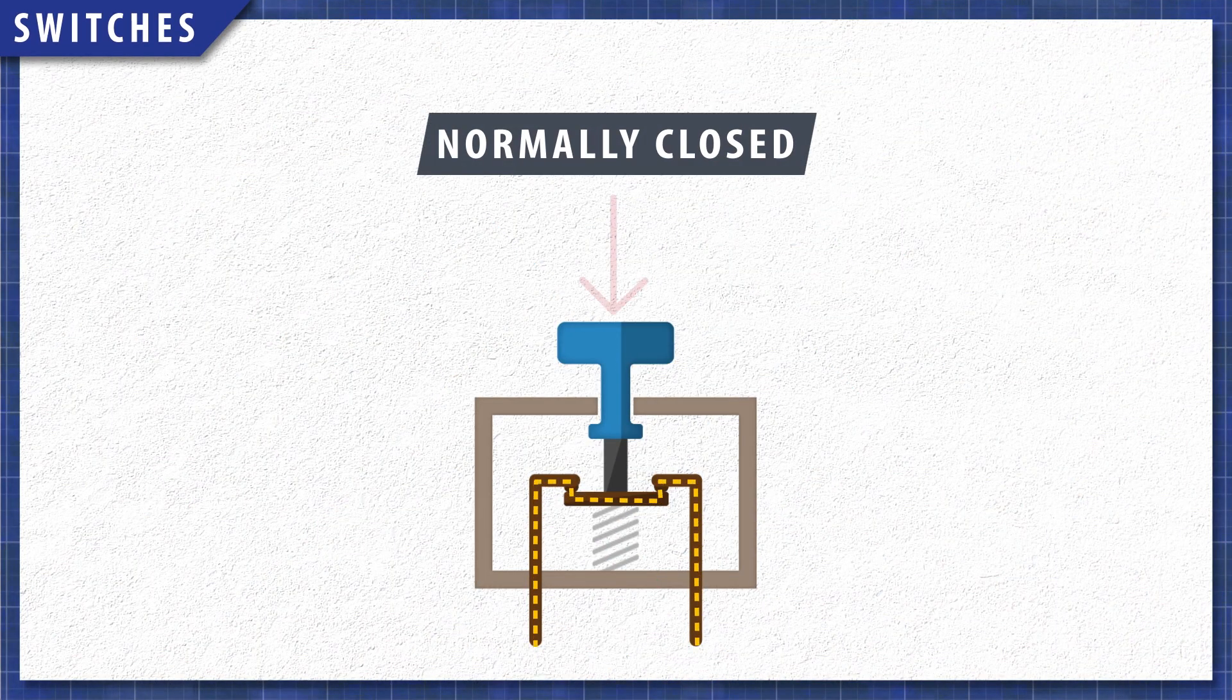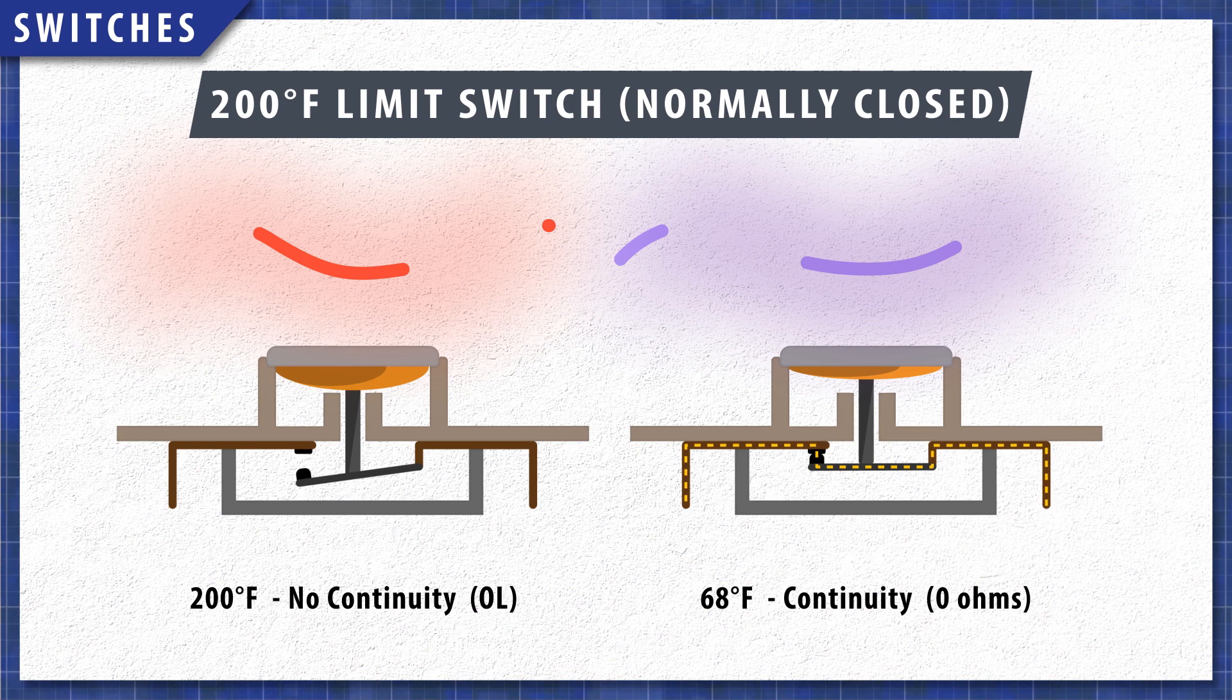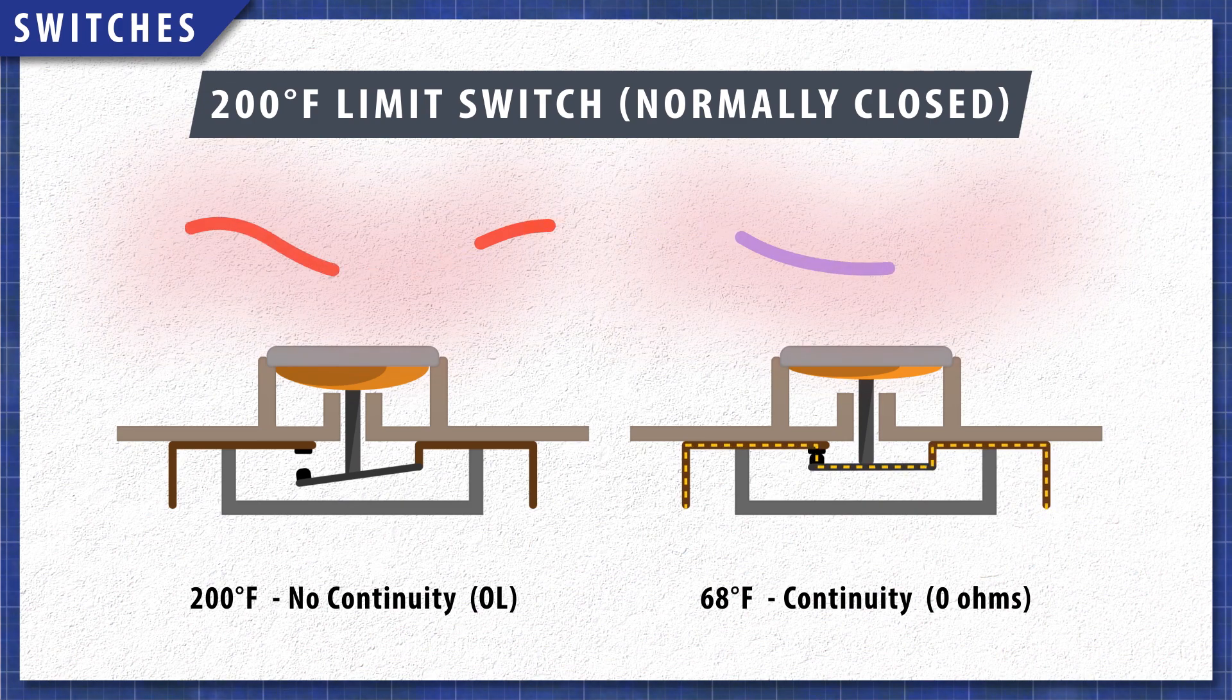Normally closed switches have continuity until the switch is opened. For example, a high limit switch rated to open at 200 degrees Fahrenheit will have continuity at room temperature.